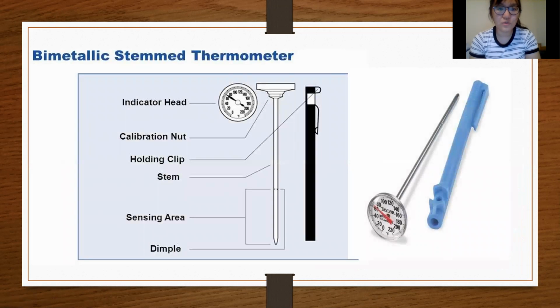So we do normally work with a bimetallic stem thermometer, and that's the one that you see on the right. What you have is the indicator head with the numbers and the temperatures and the needle. So it normally ranges from 0 degrees to 220 degrees Fahrenheit. Underneath that a little bit, you'll have the calibration nut, which is what we'll use to adjust the temperature, and I'll show you guys how to do that later on.